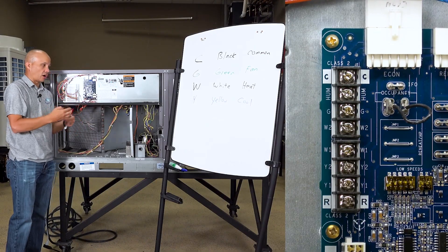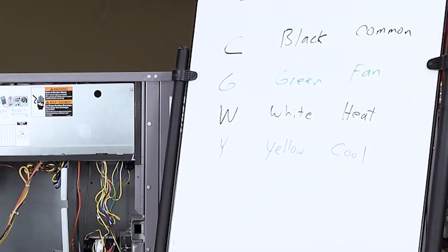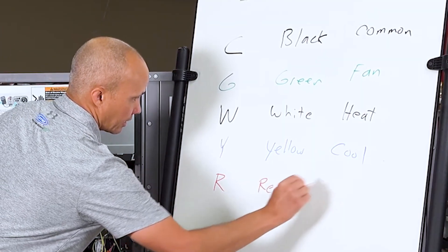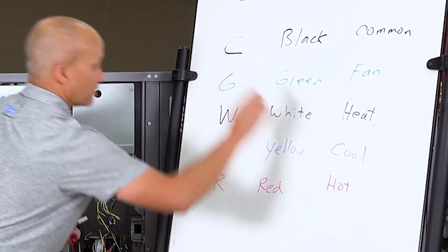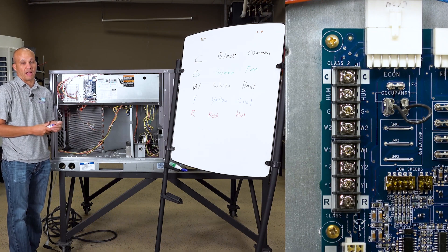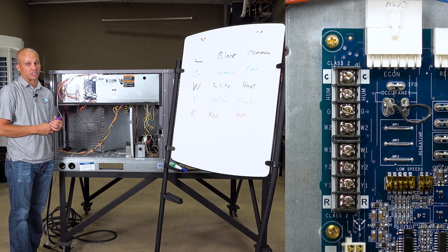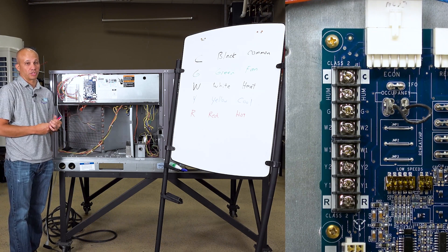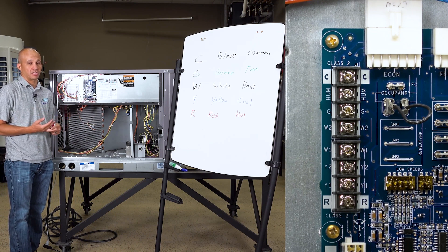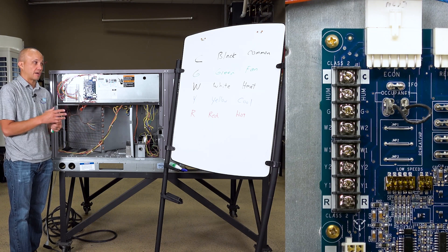And then the last one down there is R, which as you probably would guess is red, and that's the hot. So one, two, three, four, five, that's my standard thermostat wiring that I'm going to have on pretty much any single stage heating and cooling unit. If you have a heat pump, that's going to be a different beast. But if it's gas fired heat or electric heat and it's one stage, this is how it's going to wire up.